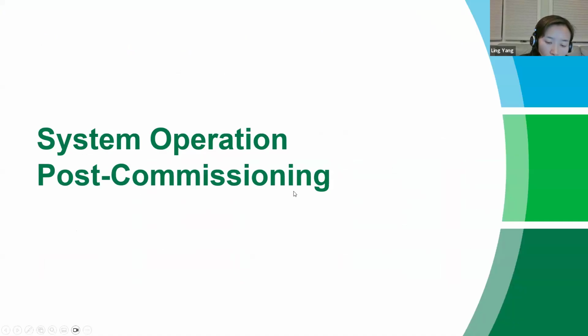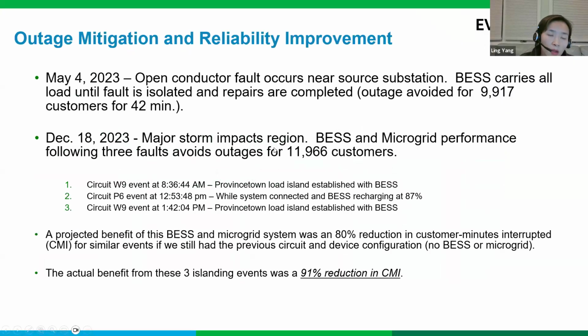These are slides our system engineering group has put together, showing some of the system operation and post-commissioning system performance. After the battery has been in service, there have been several faults in the system, and also the battery kicked in to pick up the load during a major event last December. Here I'm going to show you how the battery has improved the customer minutes interrupted index during some of the distribution faults and also during last year's storm.